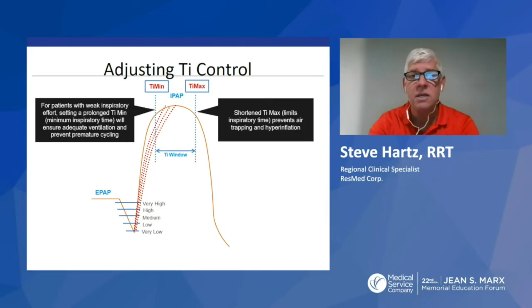Now you think about TI maximum, or maximum time in inhalation. It limits the inspiratory time. We talk about preventing air trapping and hyperinflation. This is one of the ones that leak can ultimately affect hugely. We talk about how many people leak. Everybody. You can time this factor out. Will there be an inhalation anywhere from 4 seconds down to the minimum, the TI min, technically, potentially? But it's based off the patient's disease. It's based off the patient's respiratory rate. And then ultimately, if you even change it just because we know this patient leaks all the time, it's going to ultimately help them stay in synchronization and avoid asynchrony.